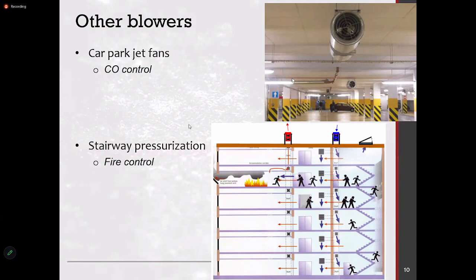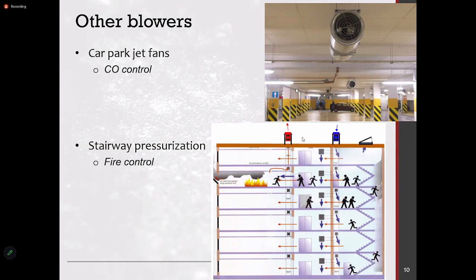So this is the particular fire control or staircase pressurization which I discussed, which is given in a diagram where you have multiple floors. So this particular floor is on fire, and there is a smoke control system also exhausting from here. So it is sucking air, where you run the exhaust fans completely. So they have designed it in such a way that you run the toilet exhaust or an additional exhaust system to ensure that the smoke inside the building is removed. And this is blowing air, and you pressurize this part of the building so that the staircase is fully ventilated and the air path is always from the staircase to the floor.